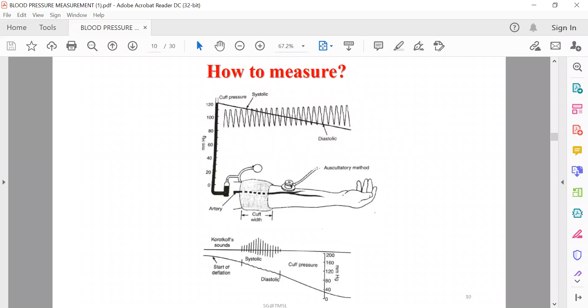Now there are certain advantages and disadvantages. The first advantage is that this method is very simple and does not require much equipment, but it has certain disadvantages also. It cannot be used in a noisy environment because you can't hear the Korotkoff sounds. So the environment should not be so noisy that you cannot hear the sound. Otherwise, you may miss the first Korotkoff sound, which is treated as the systolic pressure, and the last Korotkoff sound, which is used for the diastolic pressure.